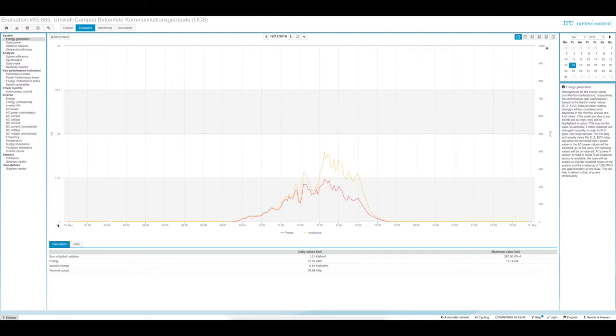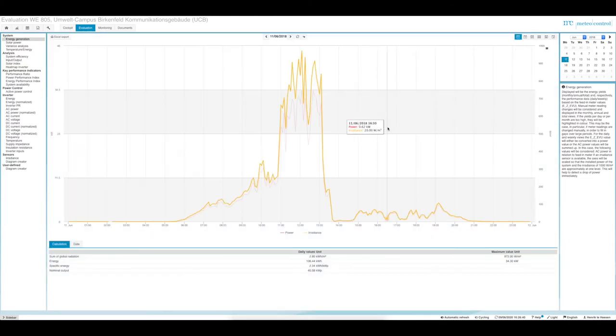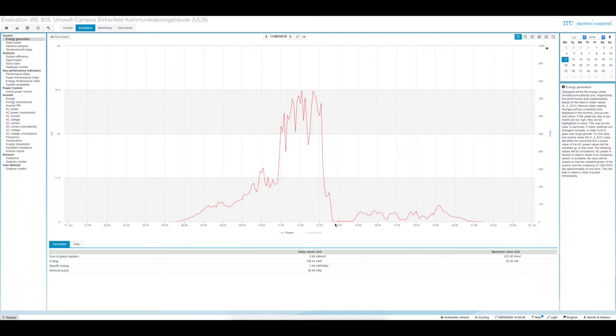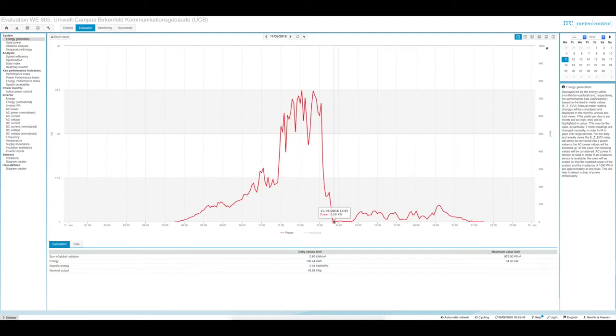The next example is what happened on the 11th of June. Think about this: if you don't have any irradiance sensor or power measurement data, you cannot decide whether there's an outage or a technical issue, or whether this is due to severe weather conditions. In this case there was a heavy thunderstorm, and you can't rely just on the power generation curve to decide what has happened at 3:45.